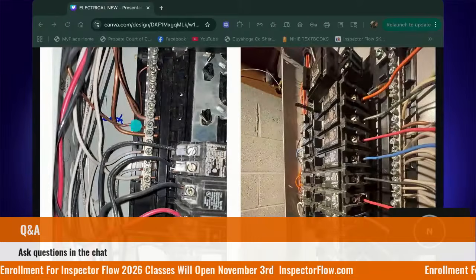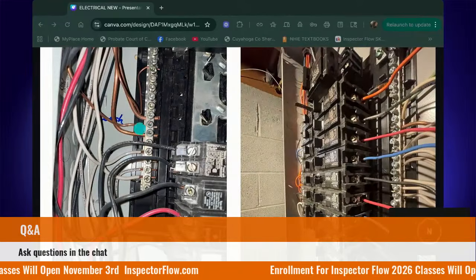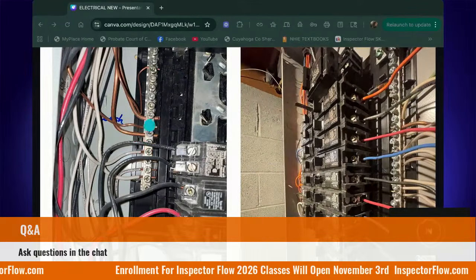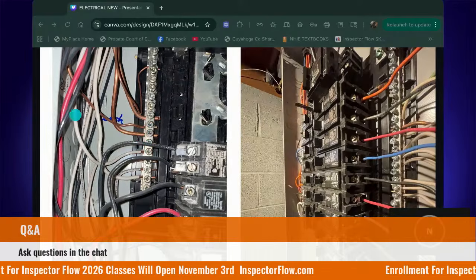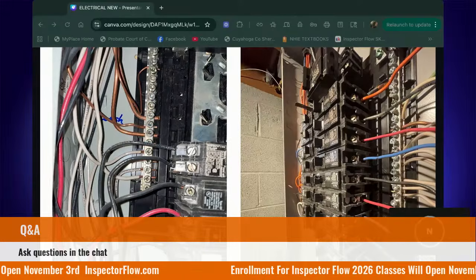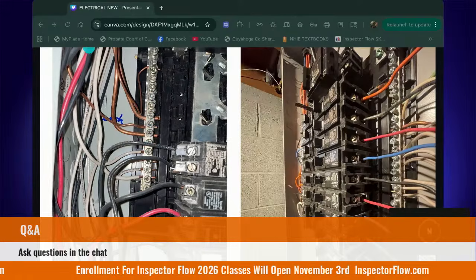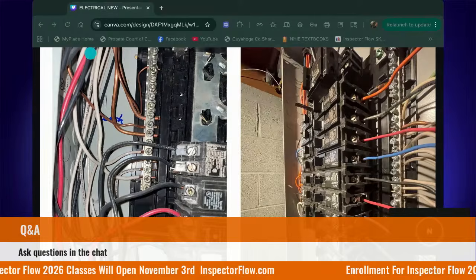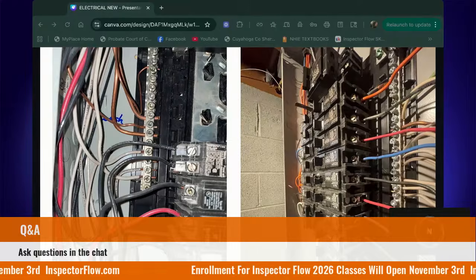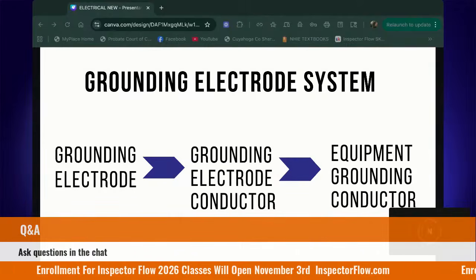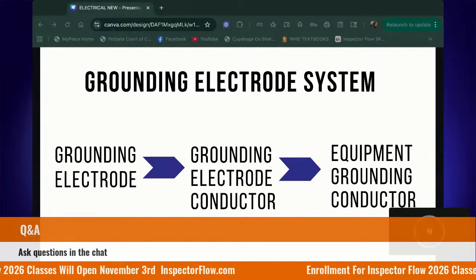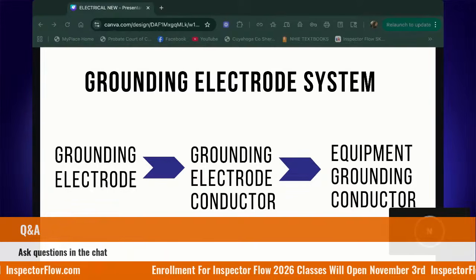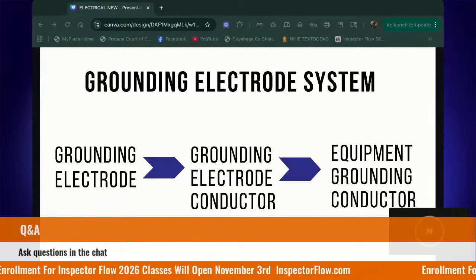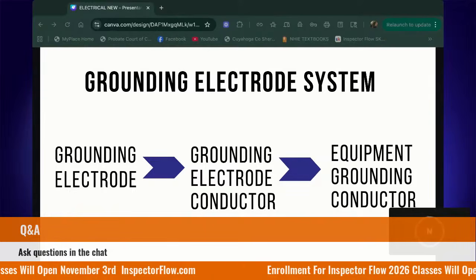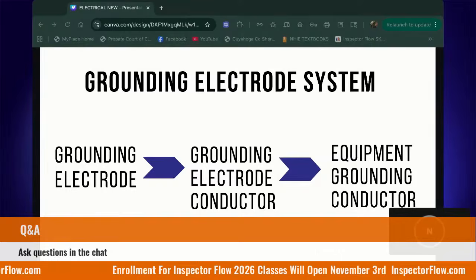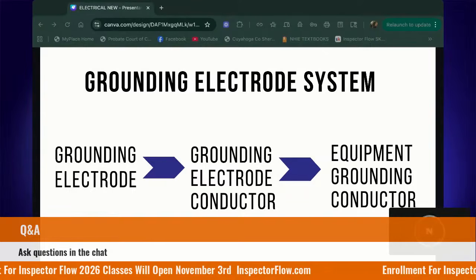So if we look at this picture here, these two here that are thicker, these are the GECs. So on one end, they terminate here on the bus bar. And then if we were to follow this all the way through, it would be connected to the GE. Grounding electrode. That's correct. Typically about a 6-gauge wire, though you won't need to know the wire size. It just has to be a thicker wire, because again, remember, we needed to be able to carry the current in the event of a fault. So it's the bridge between the wiring system in our home and the earth.